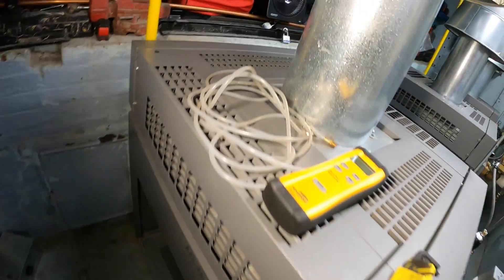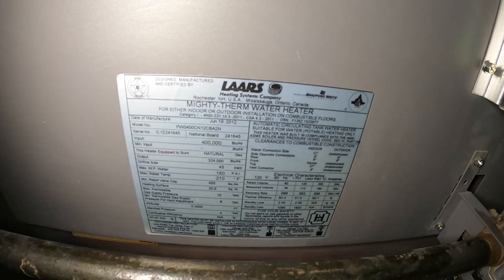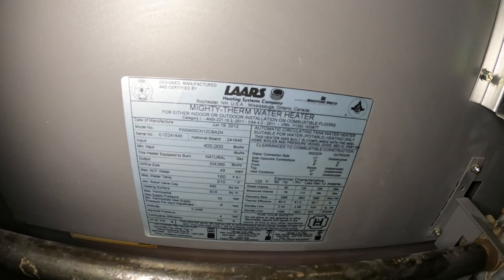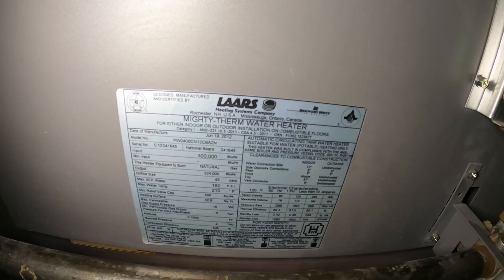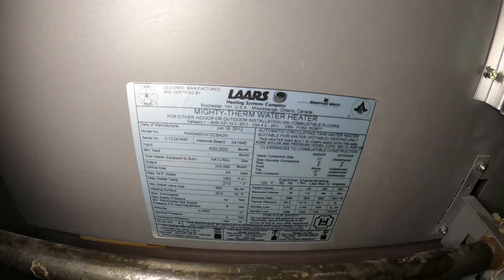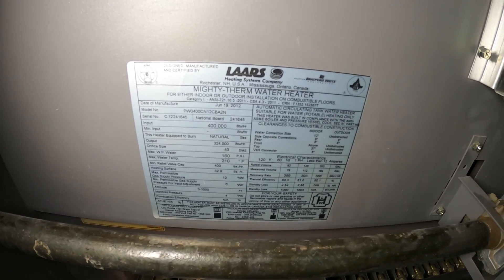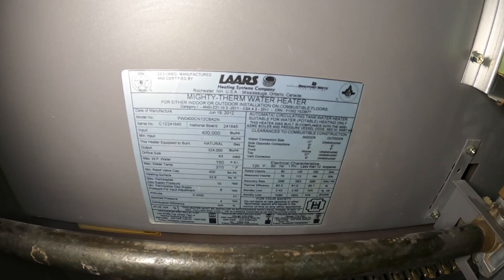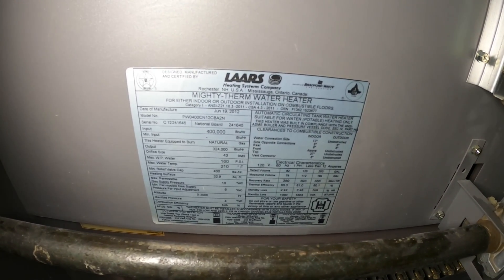This is a LAARS hydronic boiler. On this tag you'll see this is a LAARS Mighty Therm water heater. This one dates back to June 19th, 2012 as far as the date of manufacture. We need to look at what is the gas supply minimums and maximums, and also what is the manifold gas pressure.